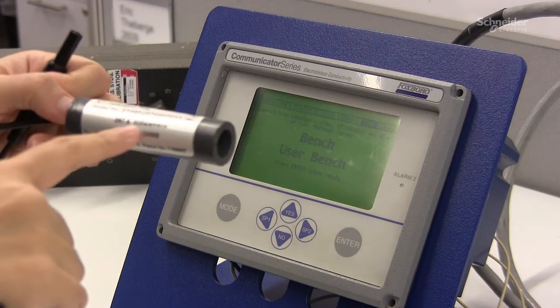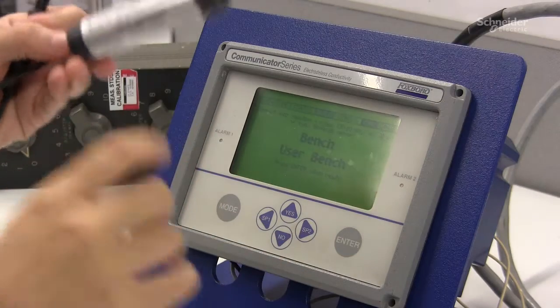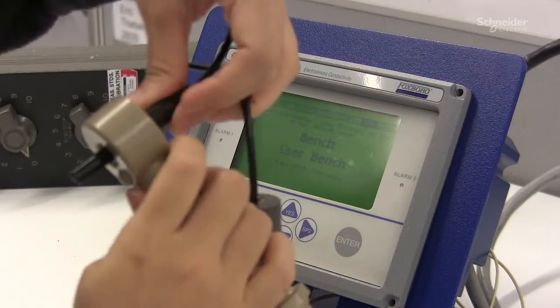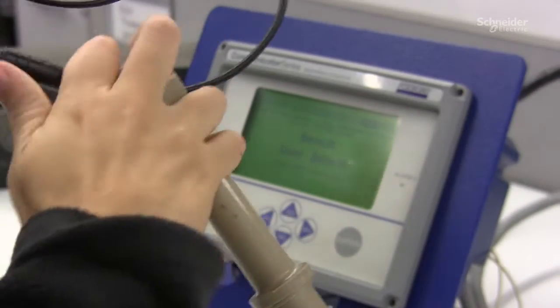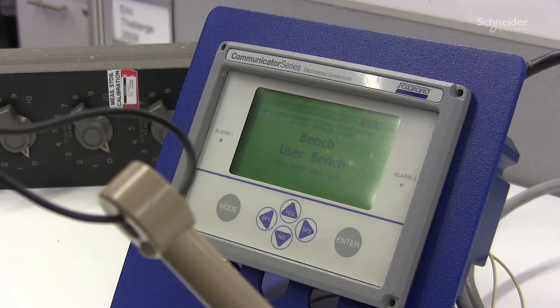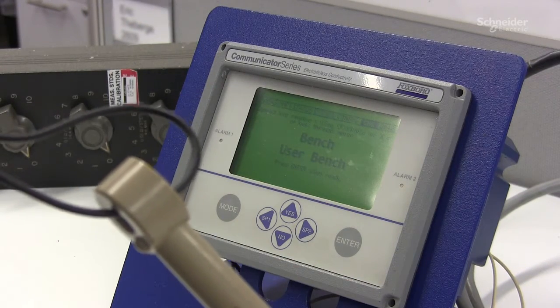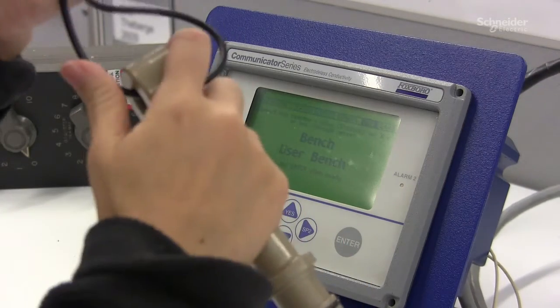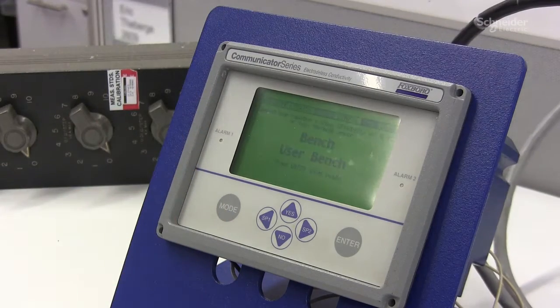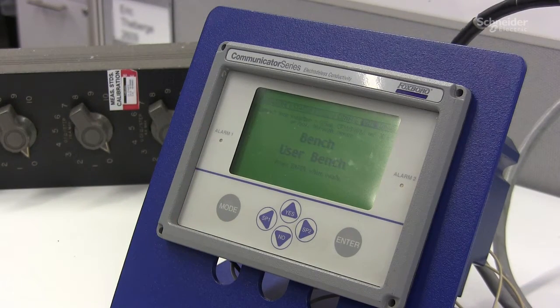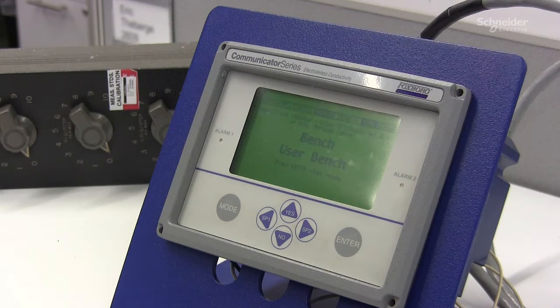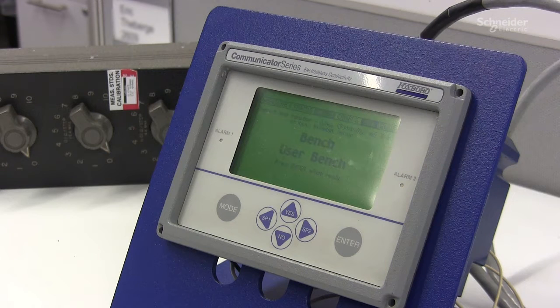Just purchase the one that corresponds to your exact conductivity limit required for your application and simply take the calibration plug, loop it to the sensor board and connect it. You will have a clear conductivity value required. But in this video we're going to assume you do not have a calibration plug, which is the preferred option, and we're going to be using math instead.